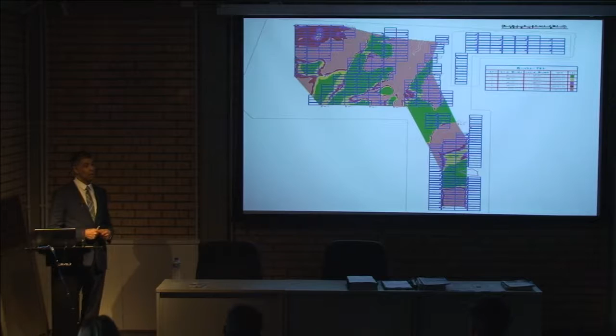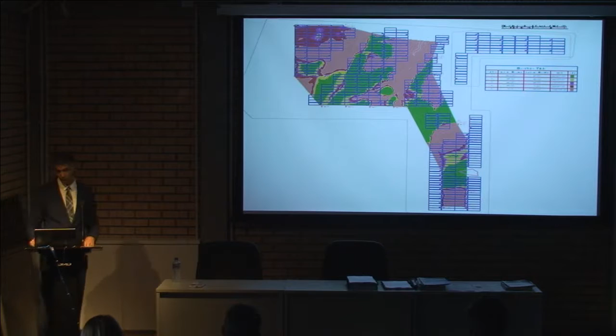Soil conditions will have an impact on your pile specifications, the weight, and you pay for the weight with money. The corrosion protection with the galvanization. It will also have an impact on the grounding grid, on the ampacity of the conductors, depending on the heat transfer capability of the soil. So there are many things that are involved with the geotechnical investigation that you need to take into account.